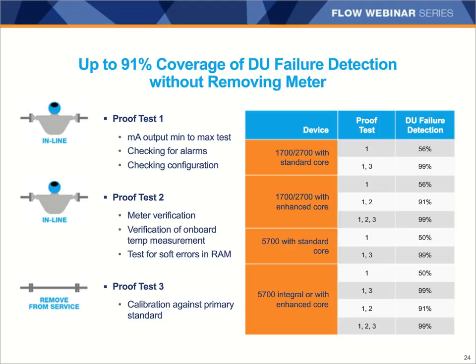However, using smart meter verification is a really good option because it allows you to get 91% of that coverage without requiring a wet calibration. This is really exciting because it can extend the amount of time between full proof test requirements and reduce the need to shut down the process, reducing the safety risks inherent in performing these non-routine operations.